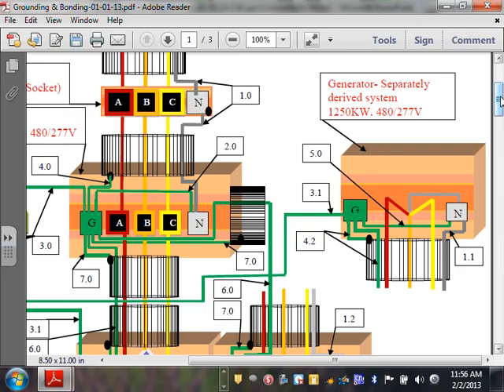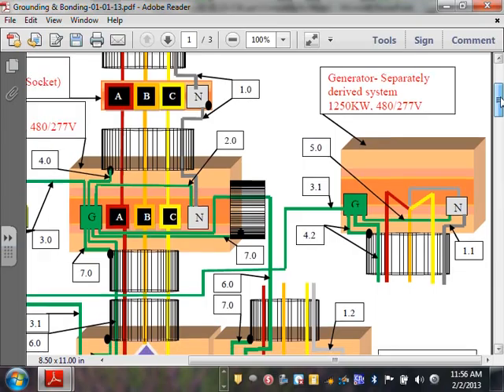Any comments, guys? Any questions? So you're also right. You put your circuit breaker on the generator. You go to the ATS, automatic transfer switch, into your panel. Now, all we're doing is taking an equipment grounding conductor between all these equipment. So that's basically what this is, guys.